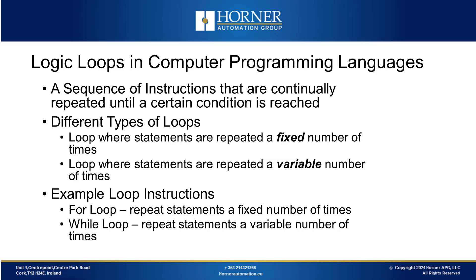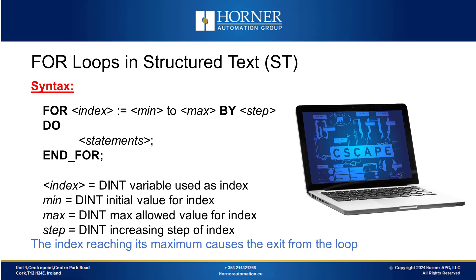Ladder logic does not have for or while instructions, so in today's demonstrations we will look at how to mimic these for and while loops in ladder logic for your application. Let's start with for loops. Here we can see the syntax for a for loop using structured text. We have built an index into the for loop, which is a starting and ending variable that through its value changes determines how many times the loop repeats. When the maximum of the loop's index is reached, we exit the loop.